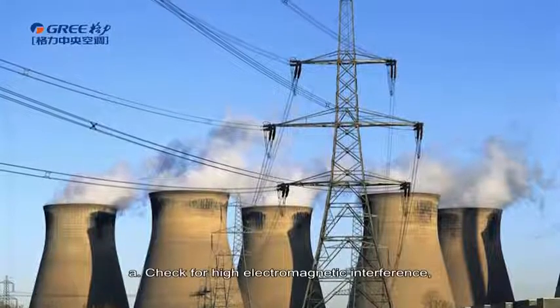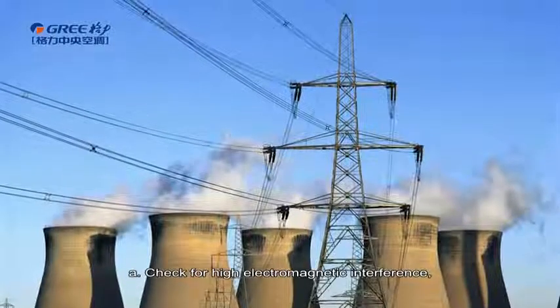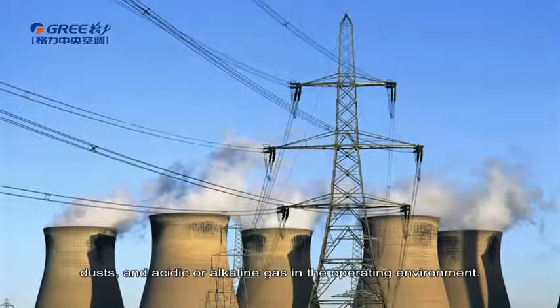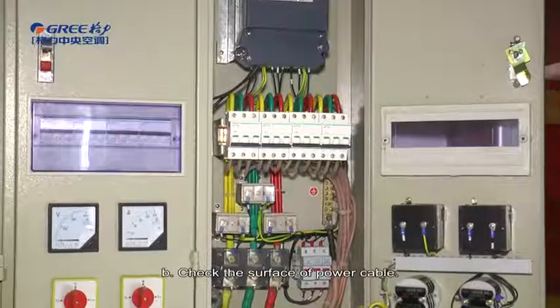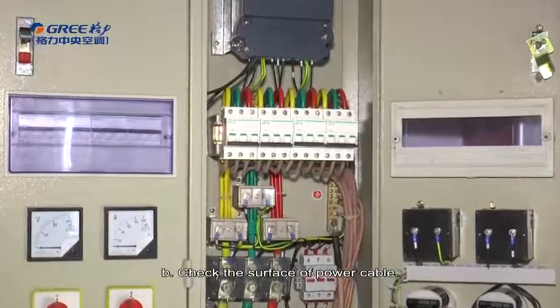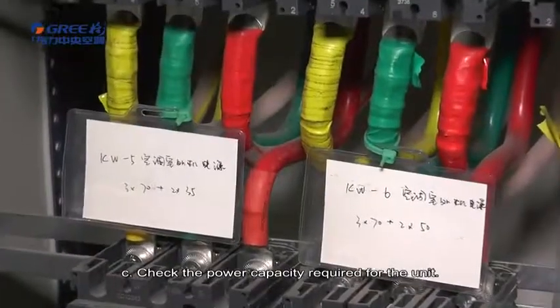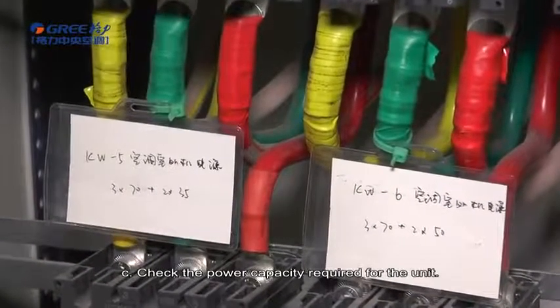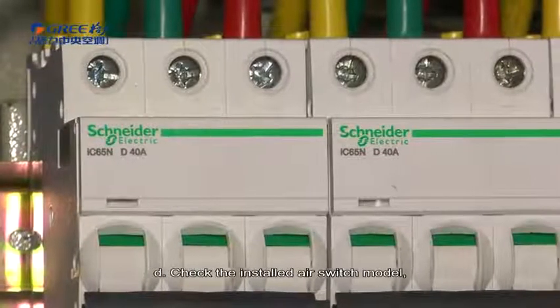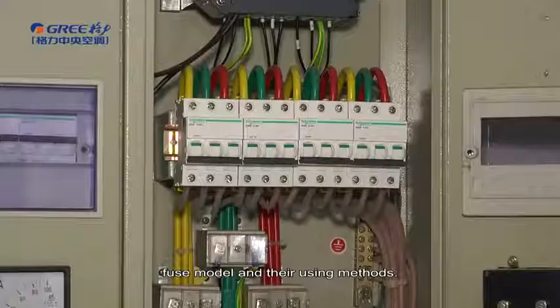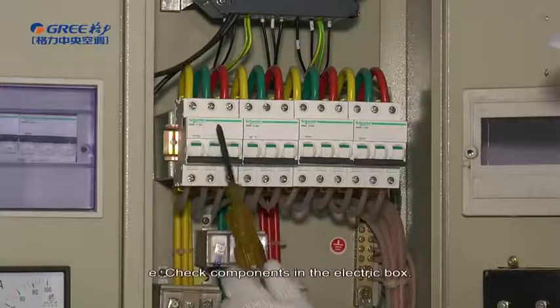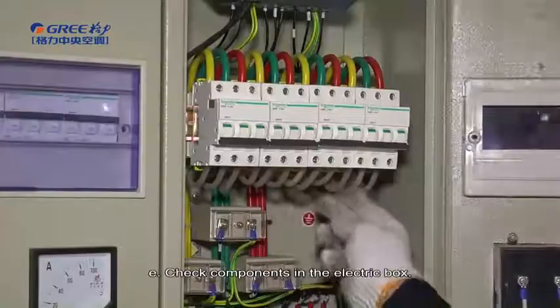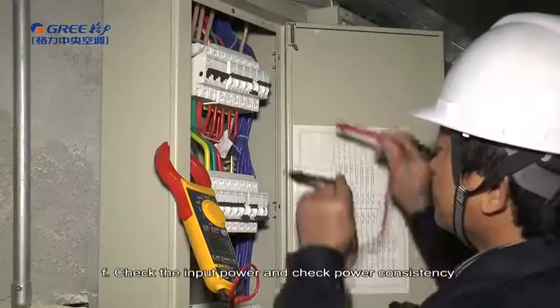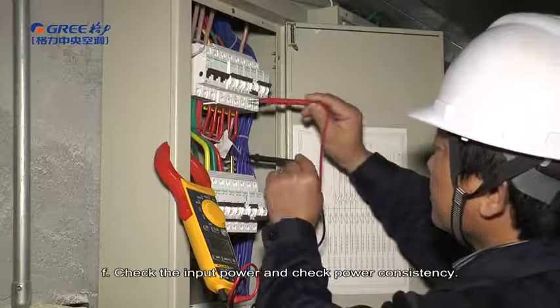Fourth, check the electrical system. A. Check for high electromagnetic interference, dusts, and acid or alkaline gas in the operating environment. B. Check the surface of power cable. C. Check the power capacity required for the unit. D. Check the installed air switch model, fuse model, and their using methods. E. Check the components in the electrical box. F. Check the input power and check power consistency.